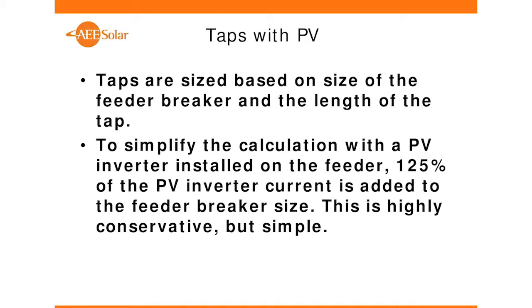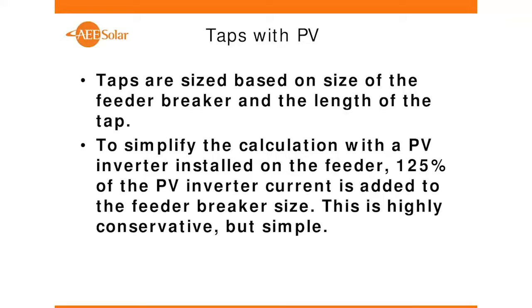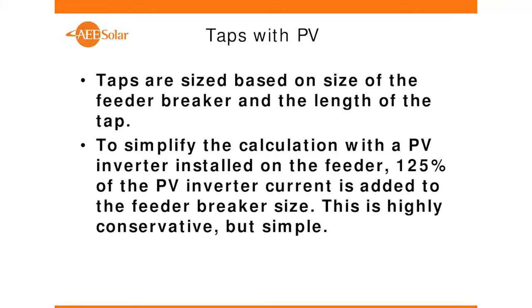Okay, so taps are sized based on the size of the feeder breaker and the length of the tap. So Article 240.21(B) talks about the 10-foot tap rule, the 25-foot tap rule, and then exterior taps. Okay, taps outside of a building. So what we did is say, okay, to be super, super simple from the standpoint of you don't have to take off your shoes or make a big argument about it, we'll just say that the PV output is adding to the feeder breaker and that the sum of those two has to be used in the calculation. The ampacity of the wire doesn't have to match that. It's just your tap rule says that if you're 10 feet or less, then you're 1/10 of the ampacity of the feeder breaker. If you're 25 feet or less, then you're 1/3 of the ampacity of the feeder breaker.